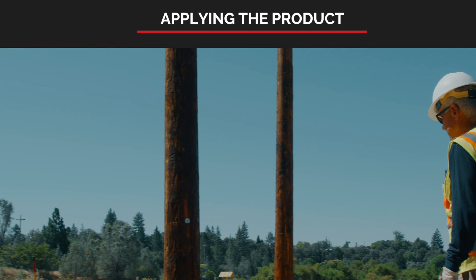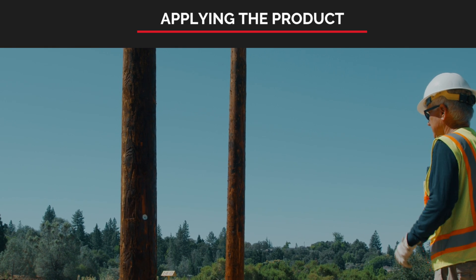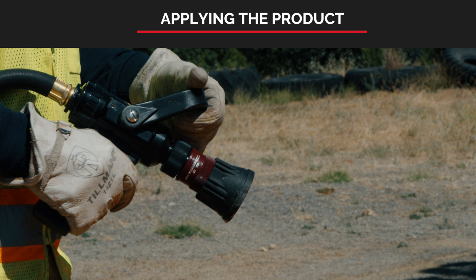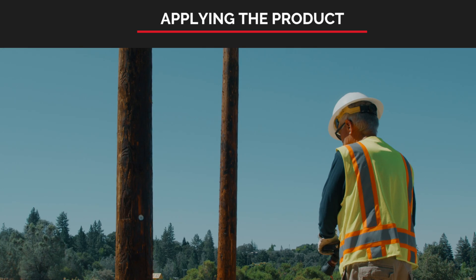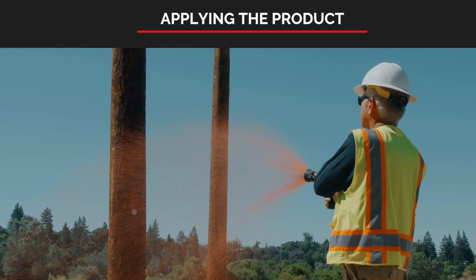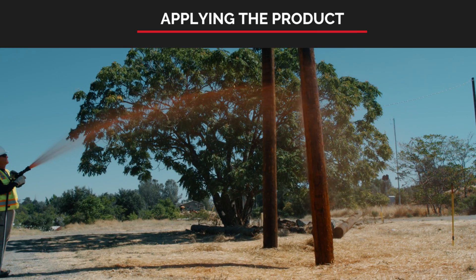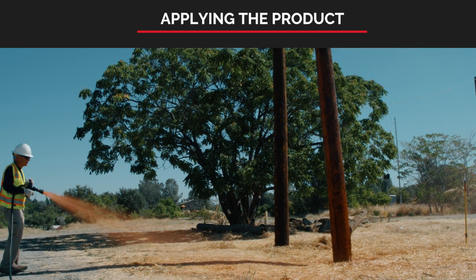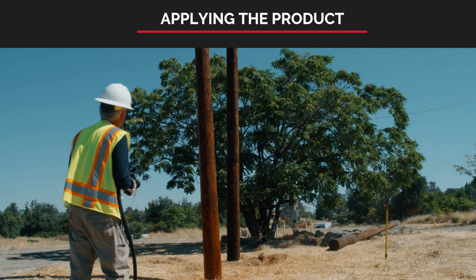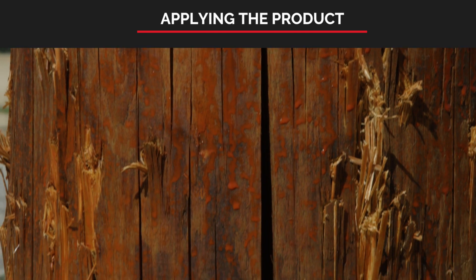Applying the retardant: Facing the pole, stand 10 to 15 feet from the pole base. Utilizing the fog spray nozzle, adjust to about a one to three foot wide pattern. Open the nozzle and begin spraying a light mist in a sweeping motion up the pole from your location. Continue spraying up the pole approximately 12 to 20 feet or greater, depending on vegetative fuel height and density. In the same sweeping motion, continue spraying back down the pole to the ground. Close the nozzle. This will provide a light coating of long-term retardant to the pole.